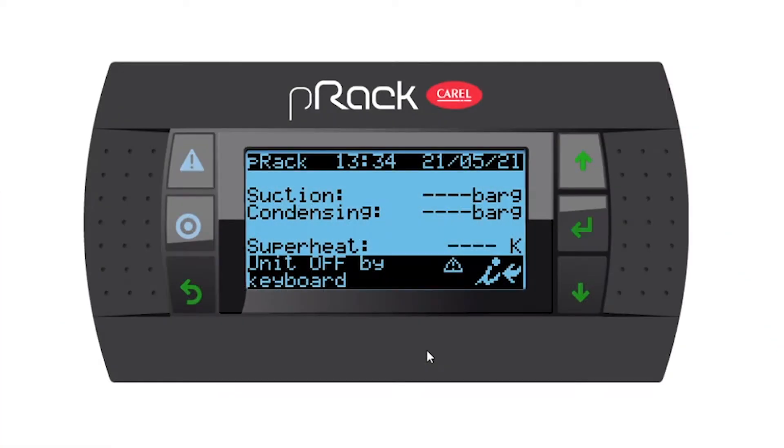Hello everyone. In this video I'd like to show you how to set up the BMS settings to communicate from the pRack controller to a supervisor or a third-party BMS. This is an alarm button, program or menu button, escape or back button, up, enter, and down.